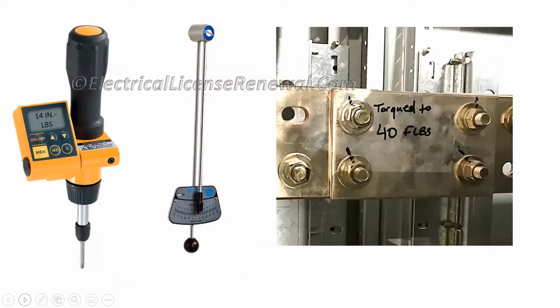So get the proper tools. And you can see here, if you look in your gear, the electricians write right on the gear: torque to 40 pounds, and you notice the little marks. That's what we train our guys to do. You torque it, then take a marker and put a stripe on the bolt. That way, when I do it and then Adam comes in to inspect, he can tell if one's without a mark -- did you torque it? Go back and check it. So we make sure all our guys put a mark on every single bolt they torque.